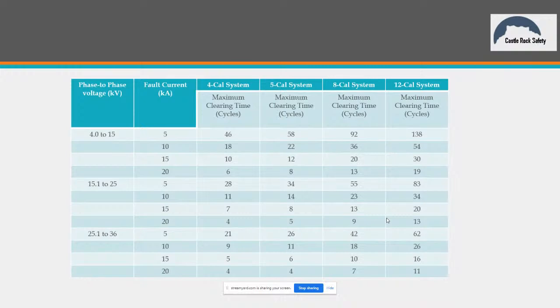Right. Okay. So now the thing you've got to keep in mind here is that for this table, the working distance that was used to determine these numbers is 15 inches. Because the assumption is that someone could be gloving that, right? And you can glove up to 36 inches, but nobody does it. I shouldn't say nobody does it. But if I'm gloving something, even at 12,470, let's drop it down to where it might be more likely to do some gloving work. So let's say you go to 4.0 up to 15 kV, I've got 10,000 amps of fault current, and a clearing time of 18 cycles. Guys, that's a long clearing time. Yeah, it is. So I've got a 4 calorie system.